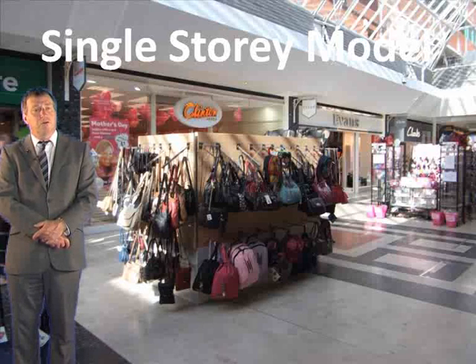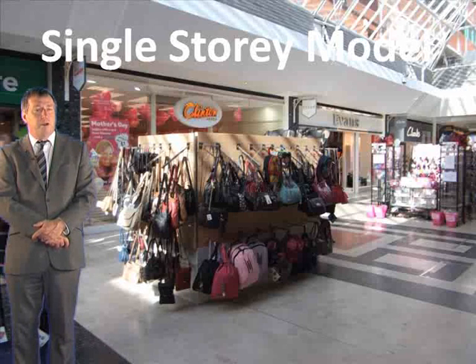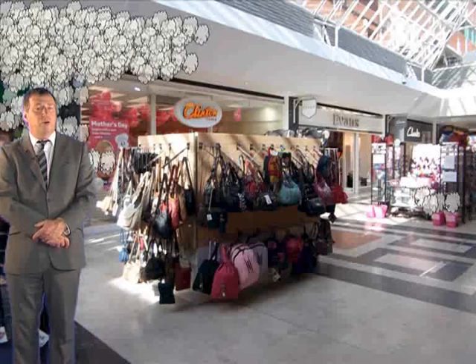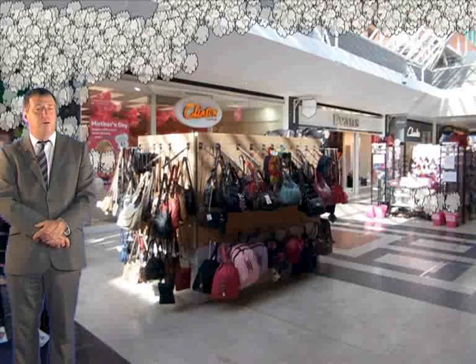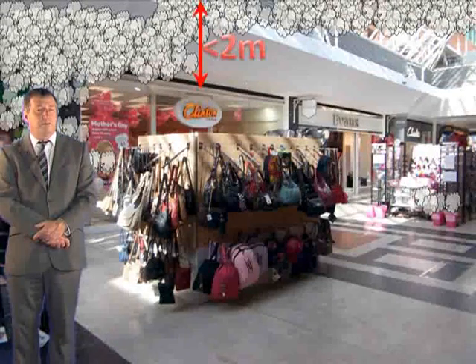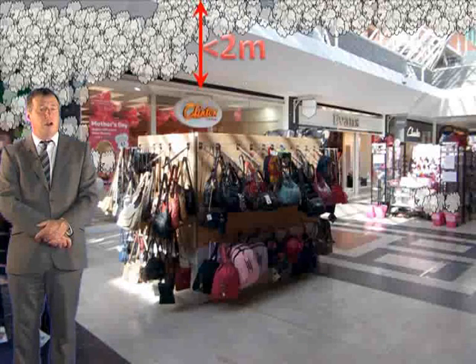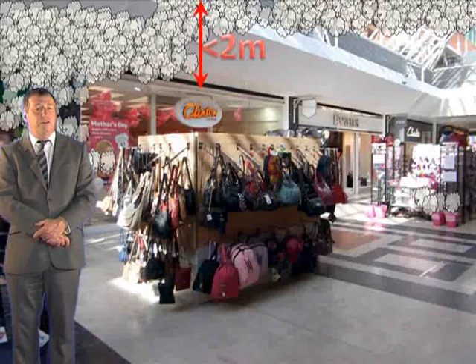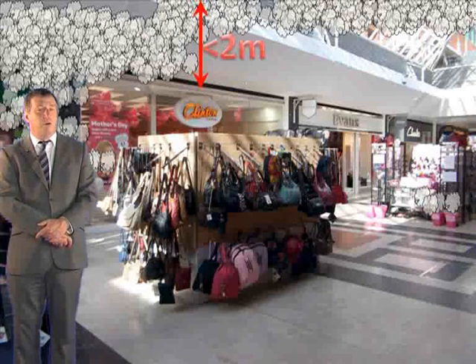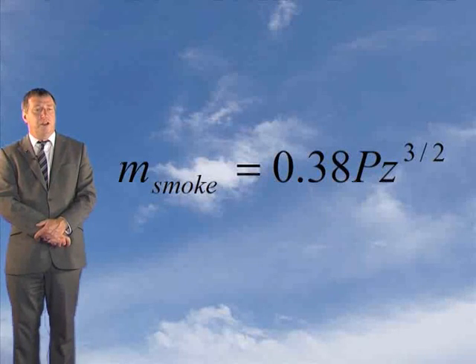We'll start by looking at the single-storey model. This is a simple model and can be used wherever the height of rise of the spill plume is no more than 2 metres. That is to say that the vertical height from the spill edge to the base of the smoke layer has to be no more than 2 metres. The model is shown here.